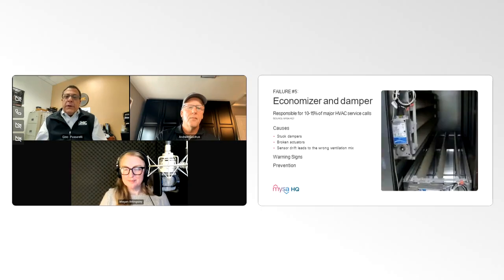I would say the things that you could look out for: economizers generally serve two purposes. One, to help bring fresh air into a public facility, and number two, to limit the air conditioning or compressor runtime when outdoor air is suitable to cool a space. And generally, there is an outdoor air sensor, outdoor air humidity sensor, and in some cases, there are indoor temperature and humidity sensors inside. So number one is if it's a colder day, fall day, winter day, and you hear your compressor running or you see your compressor running and you know that you have an economizer installed, that could be a number one sign something is not correct.